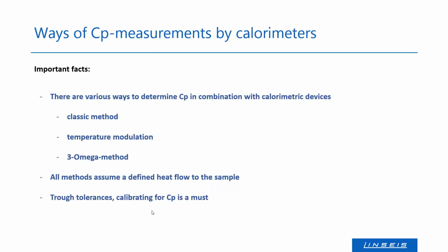Well, there are different ways to determine the CP with calorimetric devices. There's the classic method, the temperature modulation we want to focus on today, and also the 3-Omega method. Of course, we measure with DSCs or calorimeters, and all of these methods assume a defined heat flow to the sample. That's the main important thing, because basically this is what we can measure with a DSC. What's also a must is the calibration for the CP. We need a reference material whenever we do this calibration, before the measurement or when we set up the device, to calibrate the CP through the tolerance of the measurement system itself.